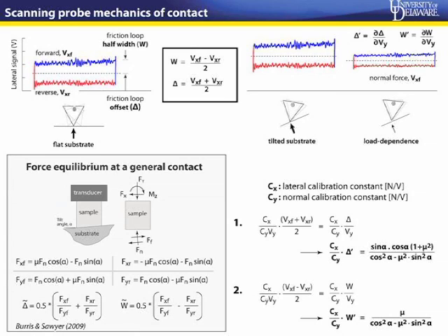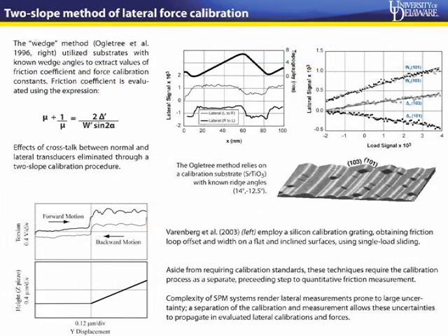Now, using this formulation of a tilted substrate, there have been a few methods that have sought to calibrate AFM cantilevers. One of them, the classical wedge method, which was proposed by Ogletree and others back in 1996, uses a calibration substrate with two known angles. They slide on these two ridges of the substrate and end up with a friction loop which goes up and down. Again, these are just changes in the offset. And if you do the load dependence, you end up with W primes and delta primes, which are the slopes of these lines.